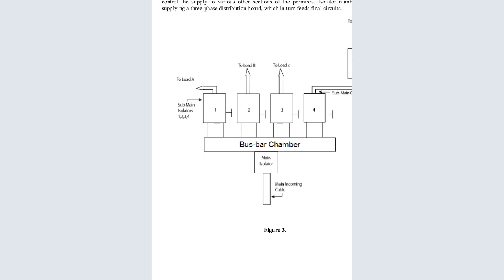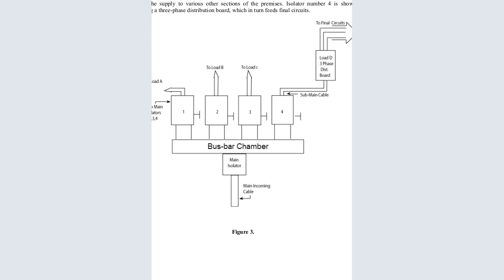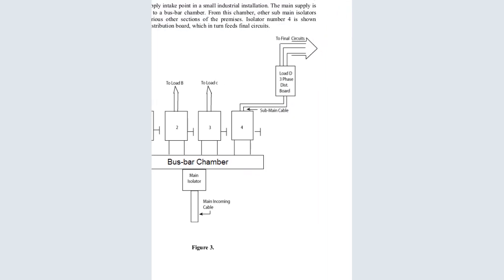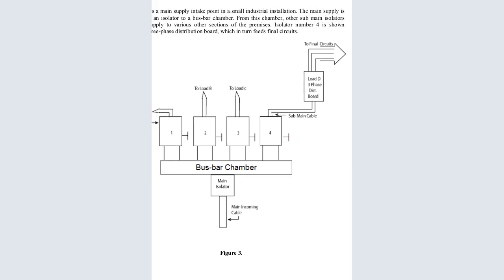So you can see this is the submains, this is the bus bar for the main isolator and the main incoming. This is called a block diagram, and we can also convert this to a schematic diagram. So we can see the sub-main isolators are here, to the loads. Then we have one to the loads, and then another distribution. These are just the bus bars that are distributing to the loads. These are to the load of the three-phase distribution board. The final circuits to other loads are there.